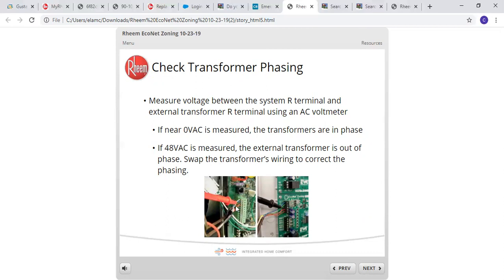So it shows you right here using your furnace board, R terminal, and then you're going to come down here to your zone board, the R terminal. So ideally you want to read 0 VAC. If you do, transformer's fine. If you read 48 VAC, the external transformer is out of phase.